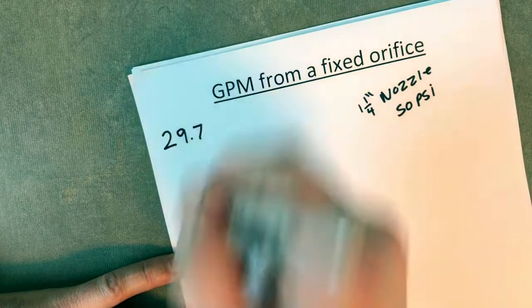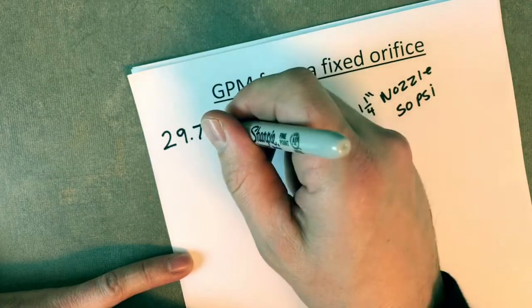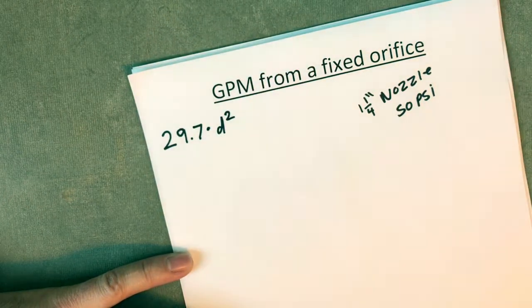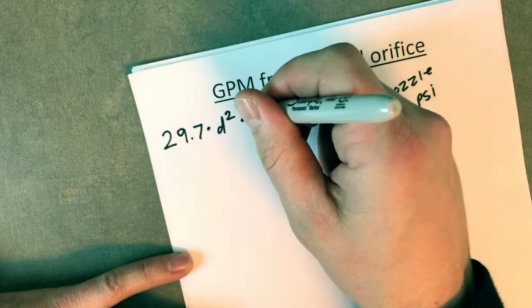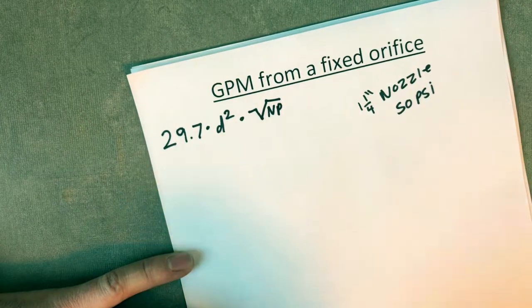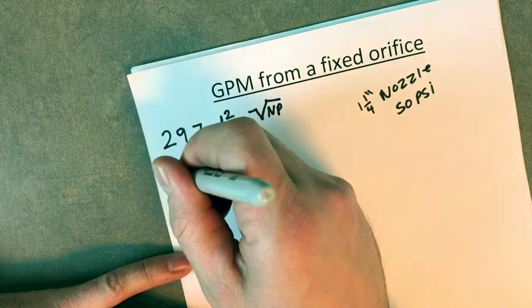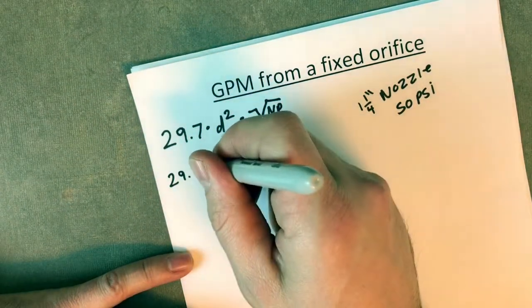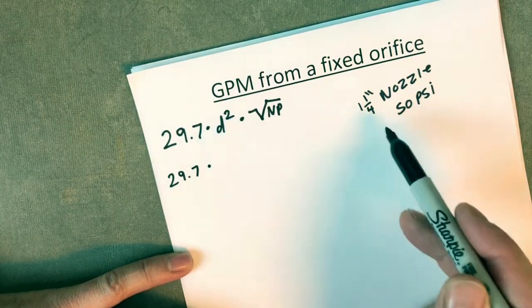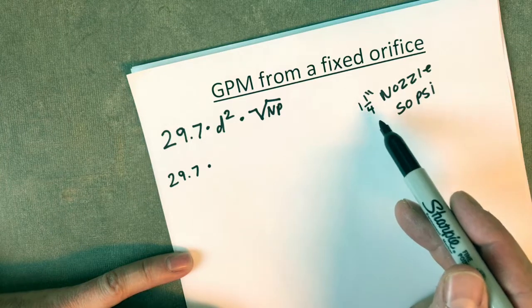29.7, which is a constant, times the tip diameter squared times square root of the nozzle pressure. So 29.7 will be our constant, times the tip diameter squared. In this case, we're using an inch and a quarter nozzle, smoothbore obviously.